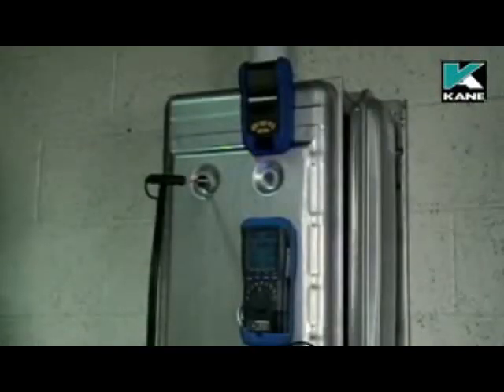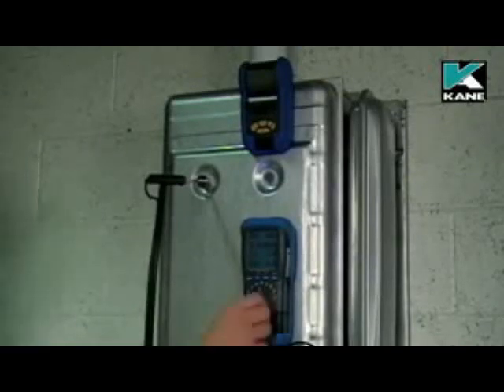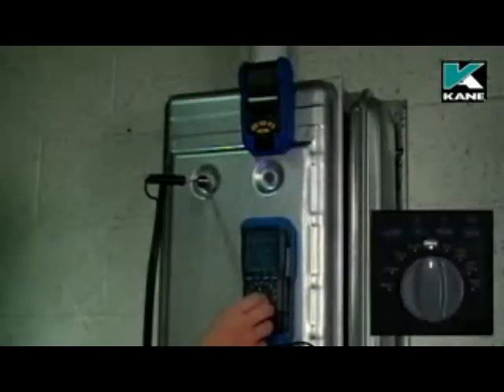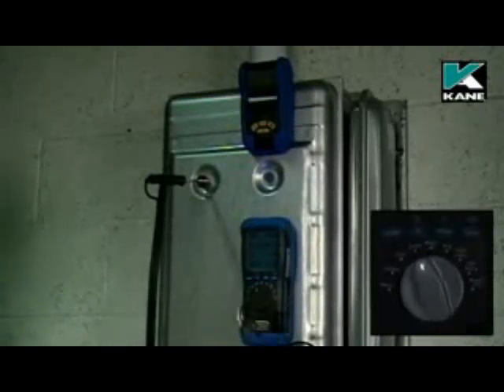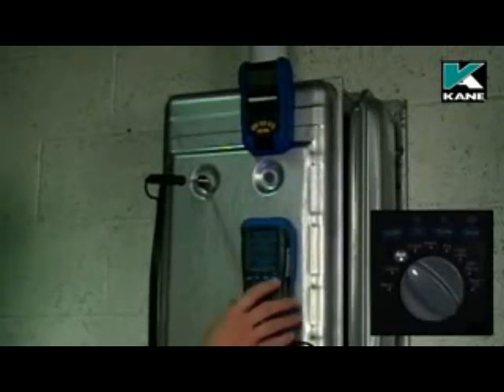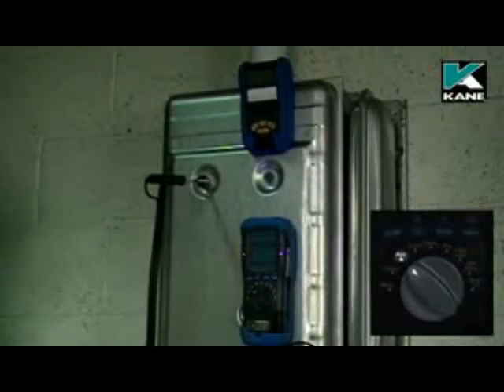When the readings are stable and you want to do a combustion printout, the rotary switch can either be in the ratio position, oxygen efficiency or the auxiliary position. Simply make sure your printer's switched on, press the send button. You must keep the analyzer and the printer lined up all the time that it says printing on the display.